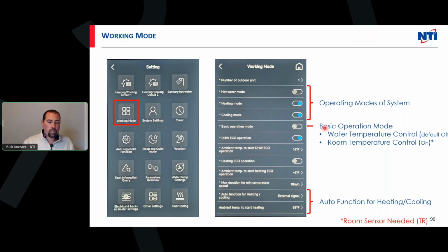Basic operation, default is off here. And basically what that means is we're going to control our system by water temperature. There is the ability to control by room temperature control. Basically then you need, as you can see at the bottom here, a room sensor that is needed. That's not a very popular way of controlling it. Usually we'll want to monitor our water temps, but if somebody is asking or looking to control it that way, we can do it.